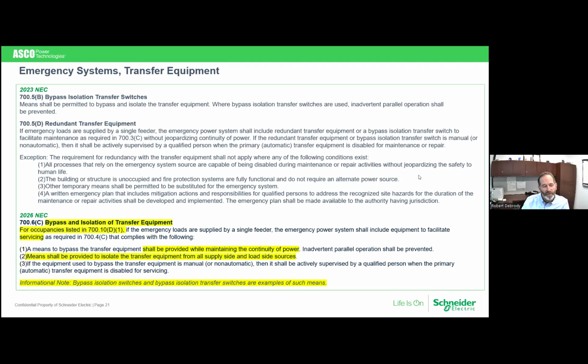The other thing that changed here was they said that if you have a bypass switch, the wording in paragraph 1 down below, they want to make sure you're maintaining continuity of power so that when you're going from the transfer switch to the backup alternate bypass switch, you're not losing power when you do that. They want to make sure you can transfer between the two without losing power. There's manufacturers out there that sell bypass isolation transfer switches. When you switch from one to the other, you lose power even for a few seconds.